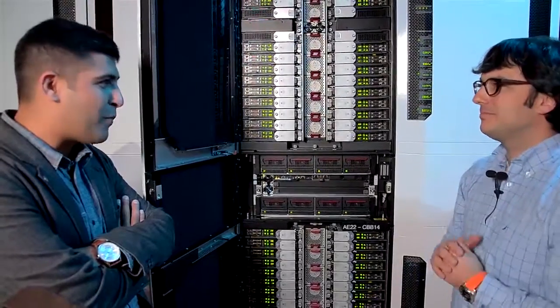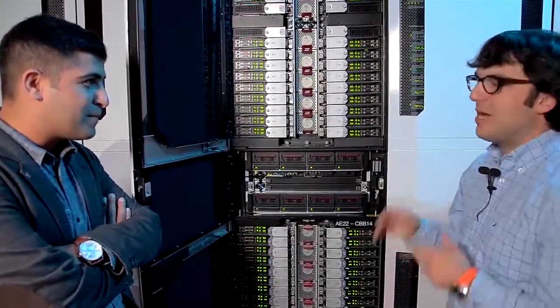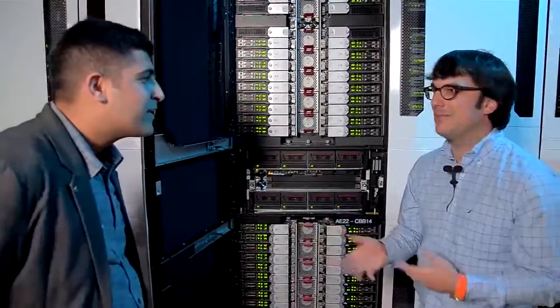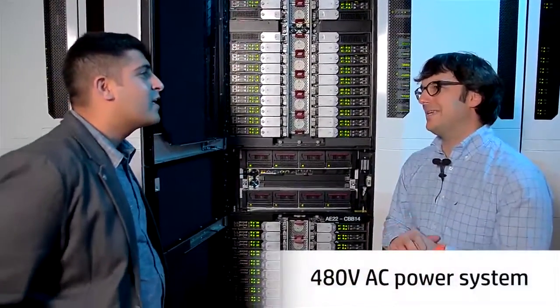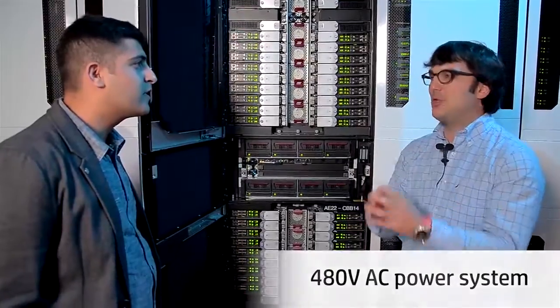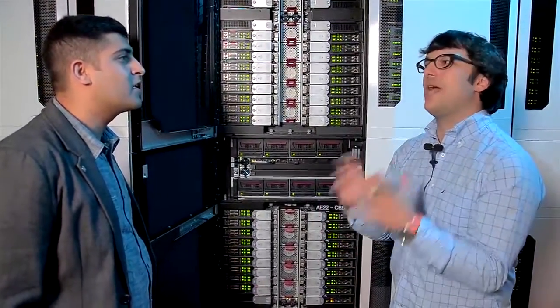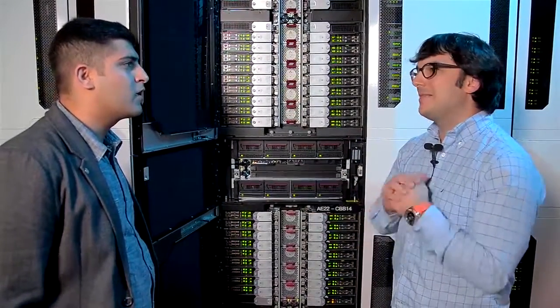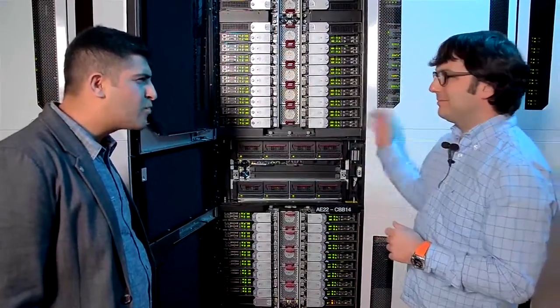How do you support the power required by these servers? The only way you can build such a dense system is to bring in 480 AC into the system. Otherwise, at 208, the wires would be way too big, and on the amp side that would be quite complicated. Does it cost more to bring that in?